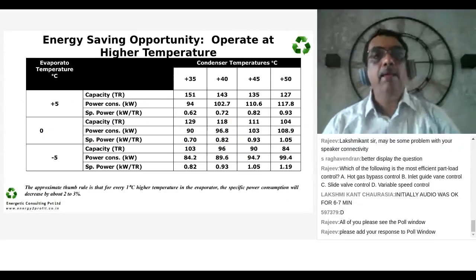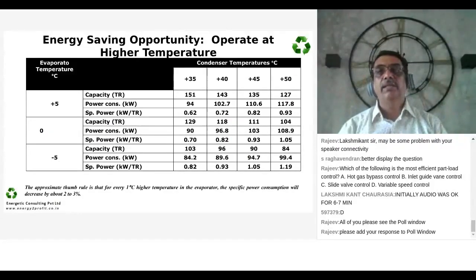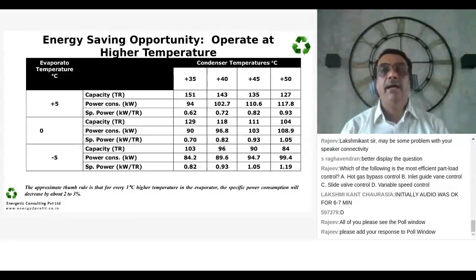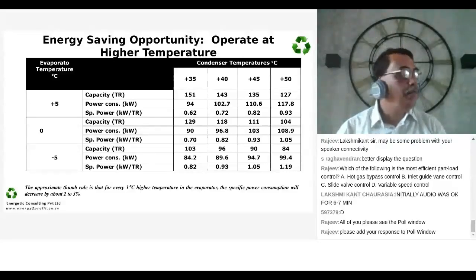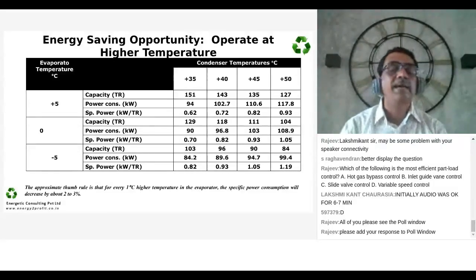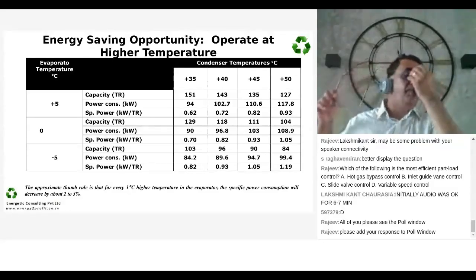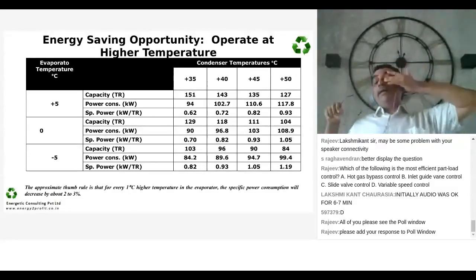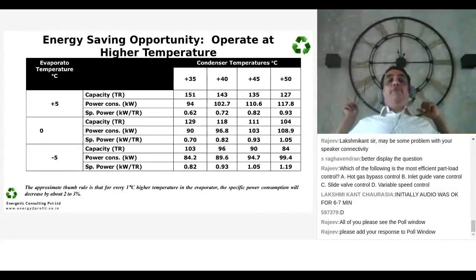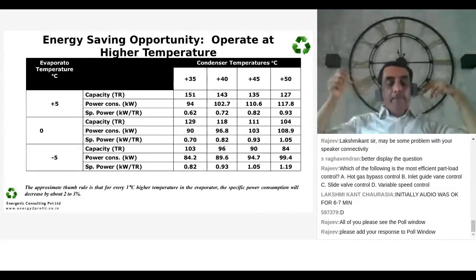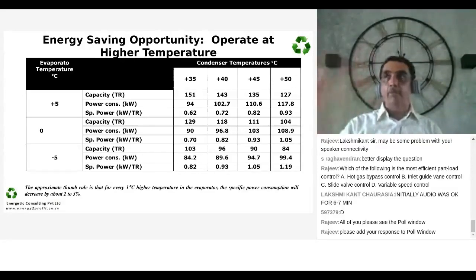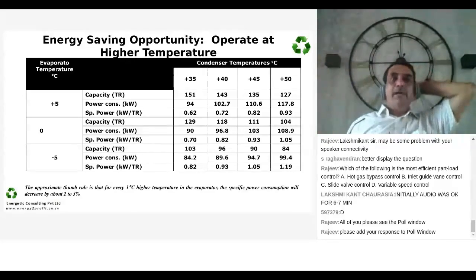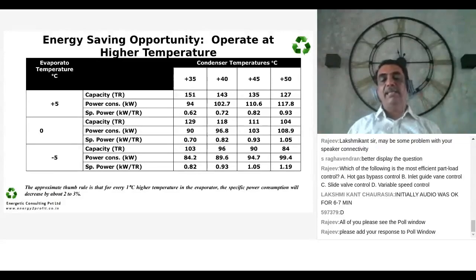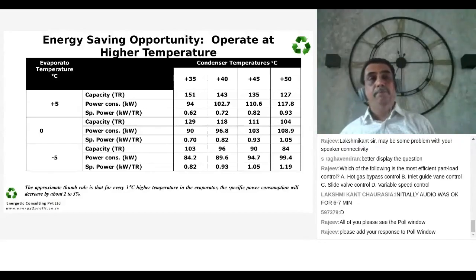Now, let's look at energy conservation opportunities. Operate at higher temperatures, which means that if you can get the same air temperature with 0 degree refrigerant temperature, it is better than -5. And if you can get it at +5 temperature, the same air temperature of 12 degrees centigrade required for air conditioning, if you can get it at 5 degrees centigrade of refrigerant temperature, you are further good.